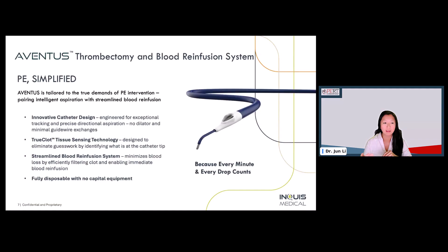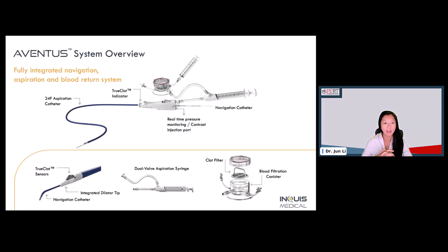Here is the completely integrated inline blood filtration system. As the clot comes into the catheter, you'll see there's a TrueClot indicator in the middle of the catheter, highlighted by a green light here. The clot then goes into the aspiration syringe, which has a specific valve that only allows one directional flow. So the blood comes into the aspiration syringe, and then as you push the syringe, the clot and the blood go into the clot filter, which you can see here. And the normal blood can then be returned to the patient. The clot sits on top of the clot filter. As we go through some of the case examples, you'll see how that comes into play in a real case. Next slide.